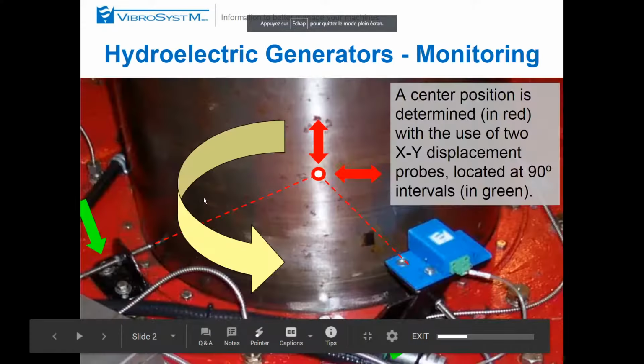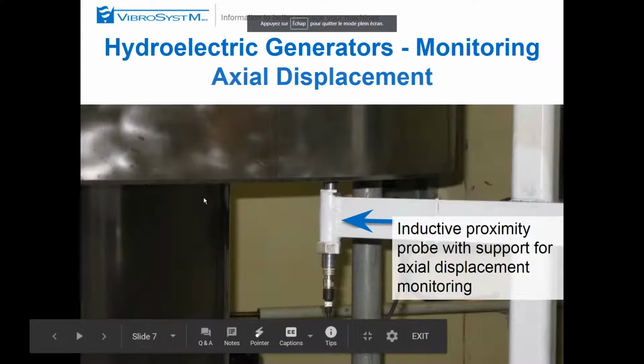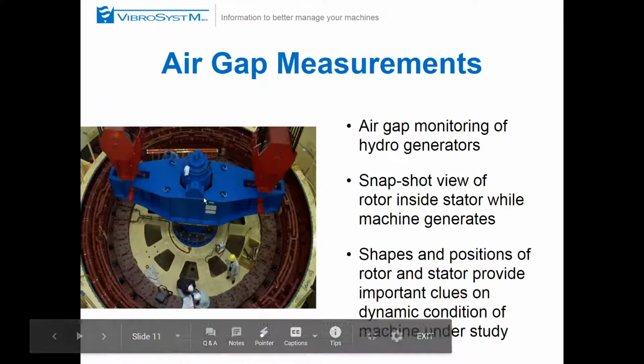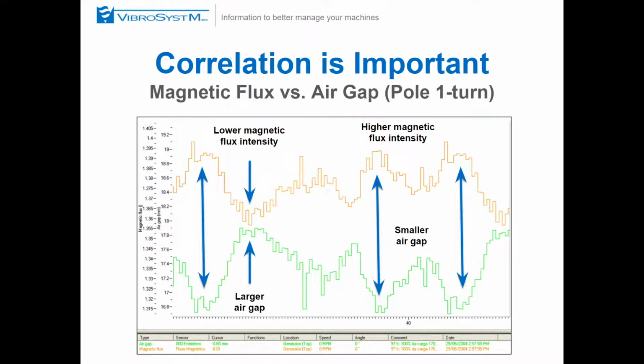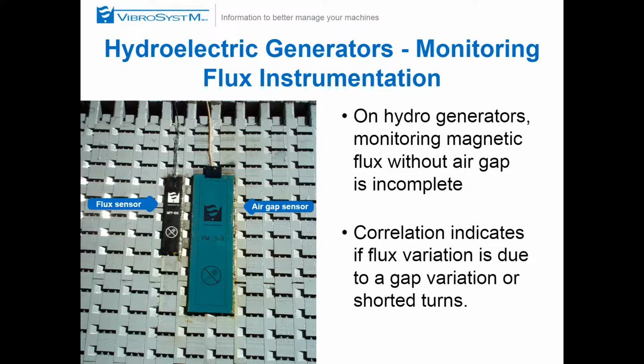So if we go back to where we were, magnetic flux. Now, in some cases, you may have some issues with shorted turns. It's a much greater issue on turbo generators, and in fact, they don't measure exactly the same thing. In turbo generators, they monitor the stray flux. They want to see the leakage flux coming off of each individual coil to see if there's any shorted turns.